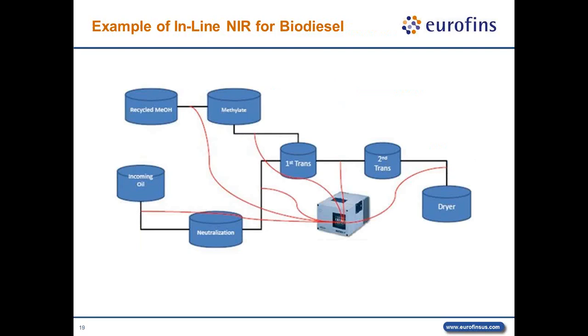Here is an example of how an inline NIR system is being used in a biodiesel facility through a very simple graphic. Here you can see the red lines represent the fiber optic cables. They are being run out from the inline spectrometer to various points in the plant where the probes would be installed and inline analysis desired. In this practical example, the plant operators would be able to monitor the quality of the feedstock being introduced to the system, the progress of the reaction, both before and after each reactor, the traits of the finished product, the byproducts, and the recovered inputs. In this case, that would be the recovered methanol.